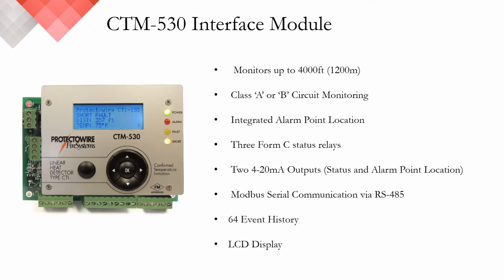Like the PIM530, the CTM530 is specific to our CTI detector and a required component with every installation. The CTM530 acts as the brain of the CTI system, providing the false alarm discrimination by comparing the pre-programmed initiation temperature with the physical temperature at the location of the fault. If the temperature at the fault does not meet the initiation criteria, the system remains in a fault condition. In a Class A configuration, you maintain continuous coverage throughout the zone. In a Class B setup, you lose only the section beyond the fault. Everything up to and including the location of the fault remains active.